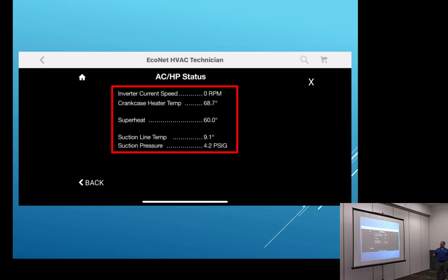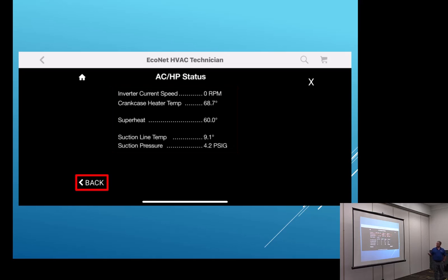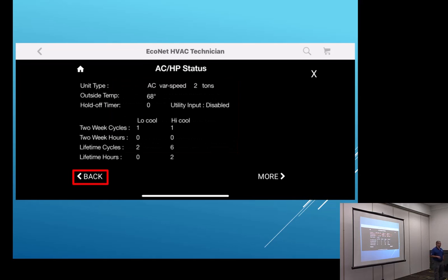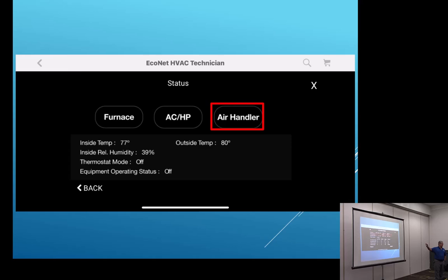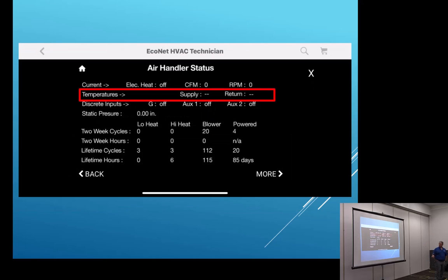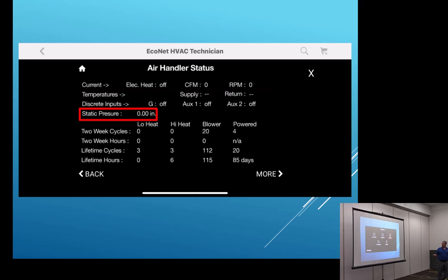You can get an outdoor status of the outdoor unit here. It tells you inverter current speed, crankcase temperature. It's got subcool and superheat with some of the updates that have come out now. You get more information here. Air handler. The air handler's got the same thing. So I may tell you, depending on what we're working on, I need a picture of the furnace status or the air handler status screen.